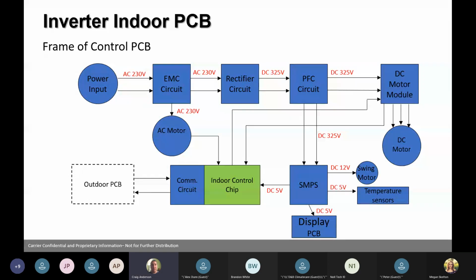Once we get into the unit, we're going from AC to DC. DC is a very low voltage. It can't be dirty. It needs to be clean, and it needs to have certain waves going through the system. So the unit needs to clean the power, and it goes through a whole bunch of different rectifiers and circuits to do that. Once it cleans the power, we go into our inverter board, and then out to our fan motor, if it's a DC fan motor, and our compressor, which is going to be DC as well. If it's a two-board system, you're going into your main board, then it's cleaning it and going into your inverter board before it goes out to any of the components.